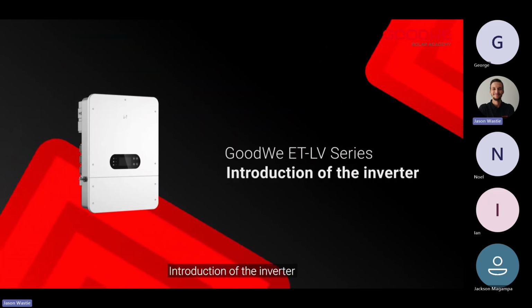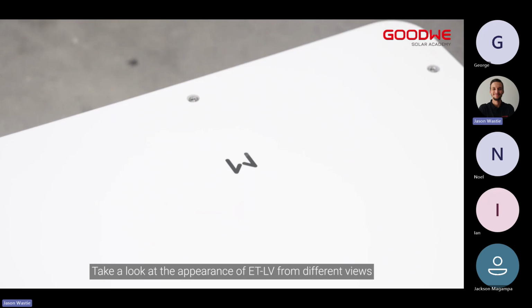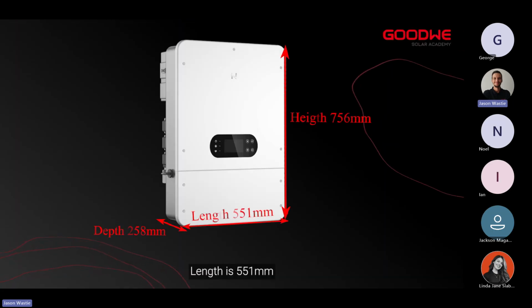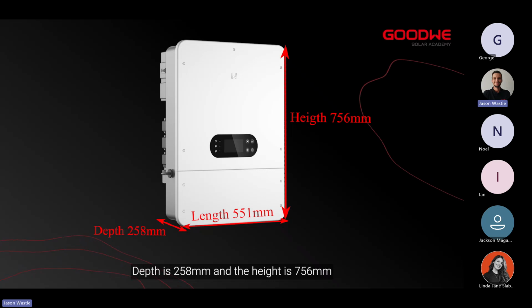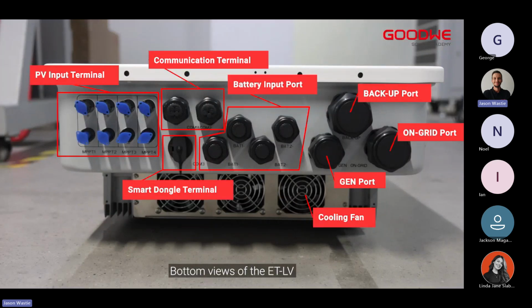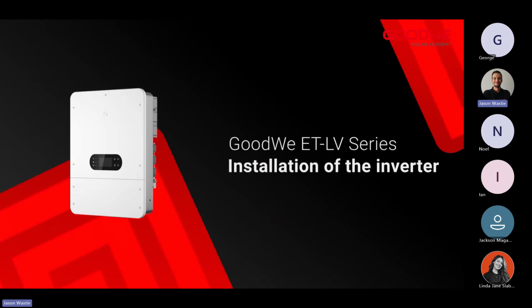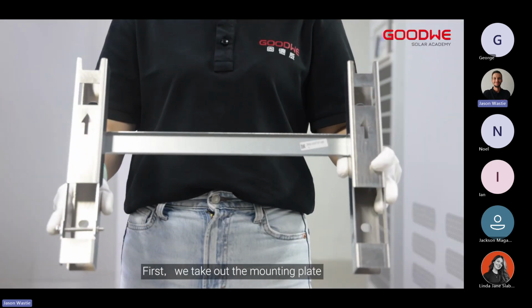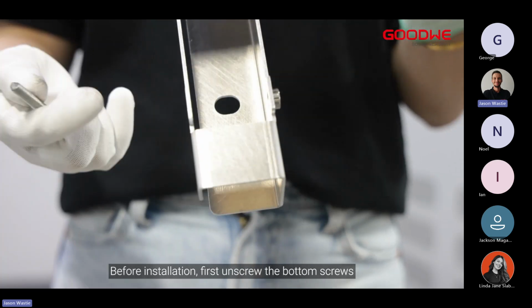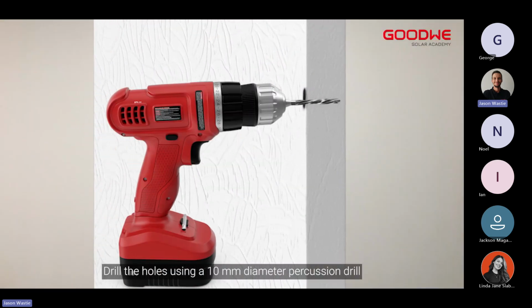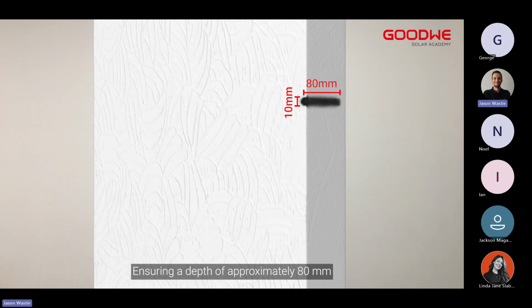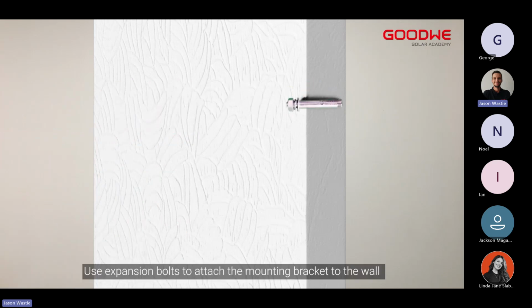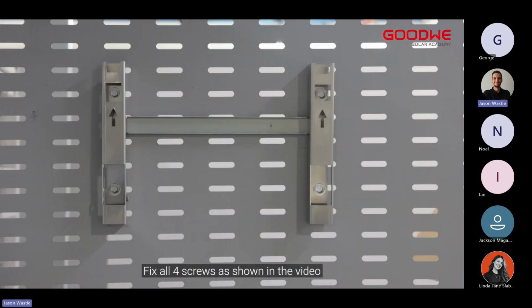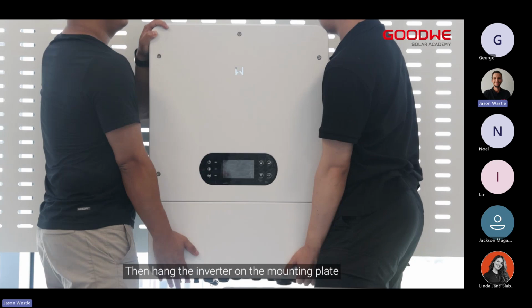Introduction of the inverter. Take a look at the appearance of ETLV from different views. Length is 551 millimeters. Depth is 258 millimeters and the height is 756 millimeters. Bottom views of the ETLV. There are many ports for different functions. Installation of the inverter. First we take out the mounting plate. Before installation, first unscrew the bottom screws. Drill the holes using a 8 mm diameter percussion drill, ensuring a depth of approximately 80 mm. Use expansion bolts to attach the mounting bracket to the wall. Fix all 4 screws as shown in the video. Then hang the inverter on the mounting plate.